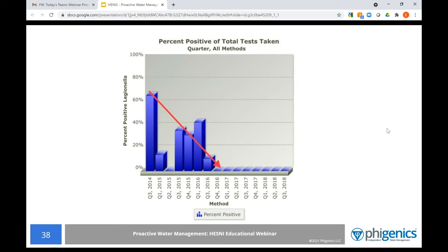And as discussed, validation is that final step to show that what you're doing is working. And so this chart shows percent positive Legionella tests to support the success of the program. You see a downward trend, and after we saw that our control limits were being consistently met, there were 0 positive detections for Legionella.